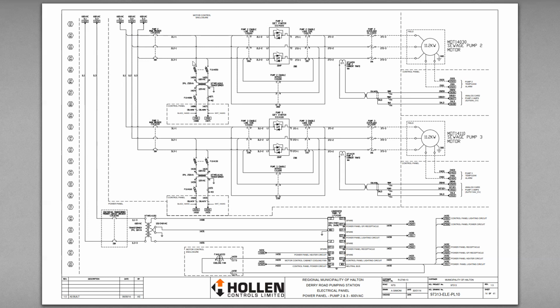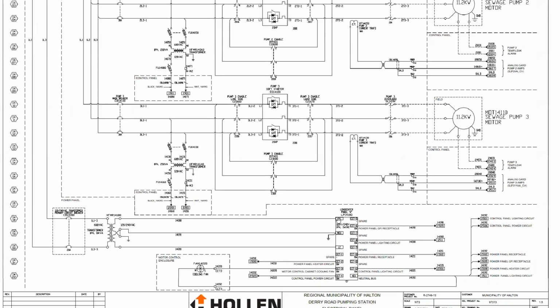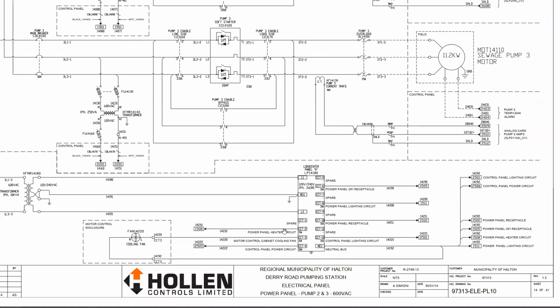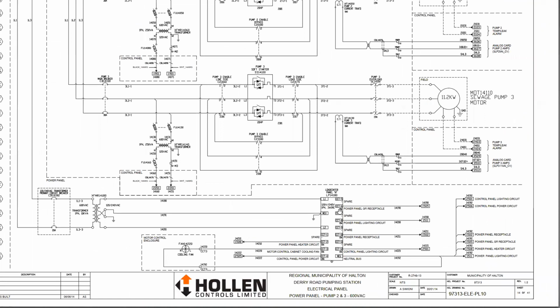We had another, so here we have another step down transformer for this pump. A little unusual to have multiple step down transformers inside of a panel, but this one did. We've got our load center panel for like supplying power to different sections. It's really a lighting panel with circuit breakers.